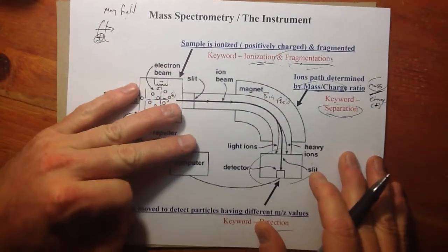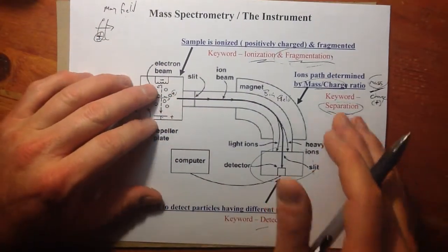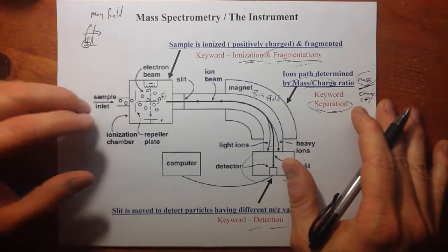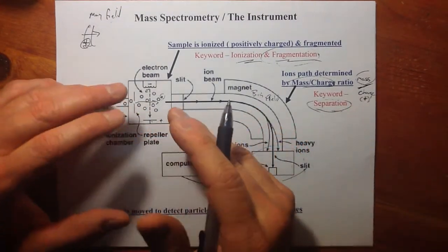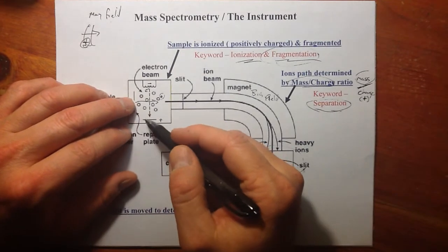So how does it work? We really have sort of three regions: the ionization chamber, the separation chamber or stage, and the detection. We have to introduce sample as a gas and in a gas phase, ionize it.